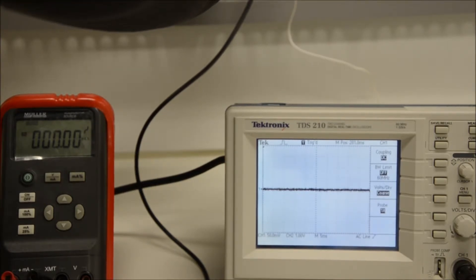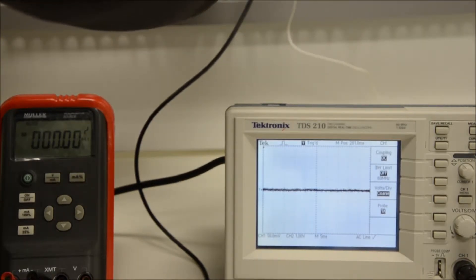With this particular thyristor it's microprocessor based and we can quite easily change between the firing modes. Get to the set menu, enter the password which is 10, and here we have the firing mode set to phase. We've now set it to burst fire and we can observe the differences.